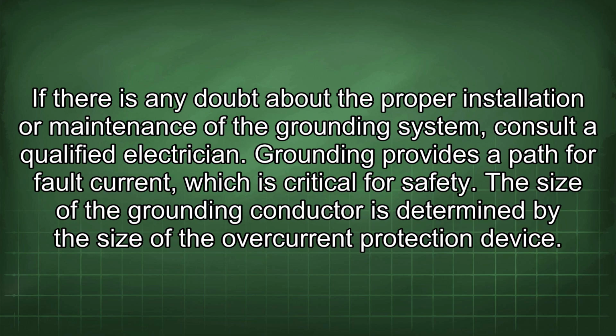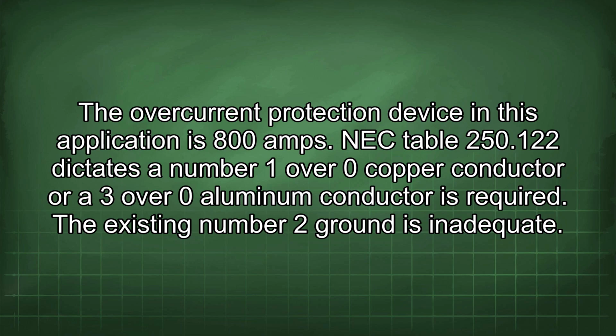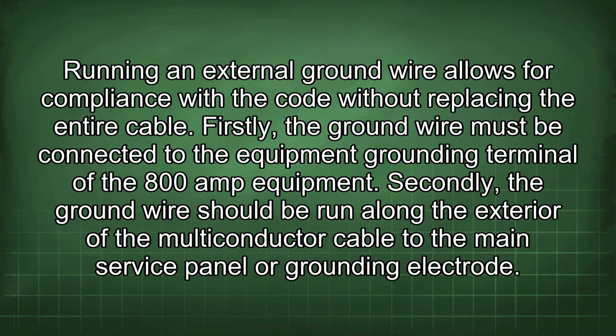Grounding provides a path for fault current, which is critical for safety. The size of the grounding conductor is determined by the size of the overcurrent protection device. The overcurrent protection device in this application is 800 amps. NEC Table 250.122 dictates a number 1/0 copper conductor or a 3/0 aluminum conductor is required. The existing number 2 ground is inadequate. Running an external ground wire allows for compliance with the code without replacing the entire cable.